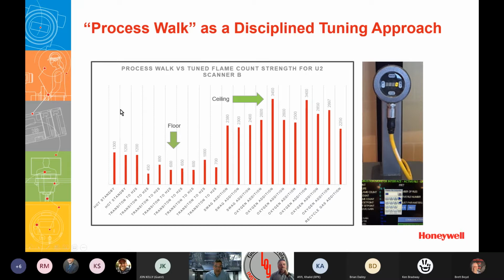Adjustments on devices that we deal with, like these industrial flame monitoring, only allows you to adjust to 3 seconds, even though you can have 4 seconds per standard. So we want to make sure that happens in order to optimize the tune on this side, because this particular process, as it ramps up in temperature 1800 plus, it goes into a process fired condition, which has different considerations, pretty much dominant on the infrared signal. So once again, flame failure response time has to do with, did I see a flame within 4 seconds?